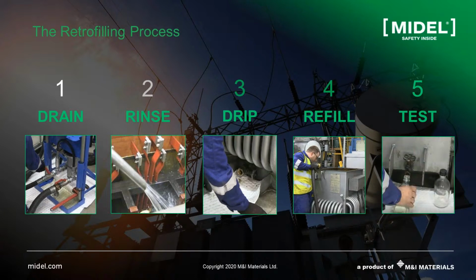And after that, step 2, I think, is one of the most important steps. That is what we call the rinse, or in other words, please do a hot flush with fresh new MIDEL, which means that after you drain out all the mineral oil, wait a little bit of time, and if you are able to open the lids or the mineral oil on the side, please rinse or do a hot flush with MIDEL, just like a washing time for the internal construction parts with this new MIDEL. Many times we would say that this additional MIDEL would mean around 5 to 10% of the whole volume. So that could give us really good results at the end.